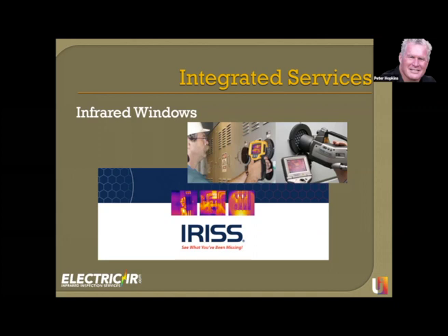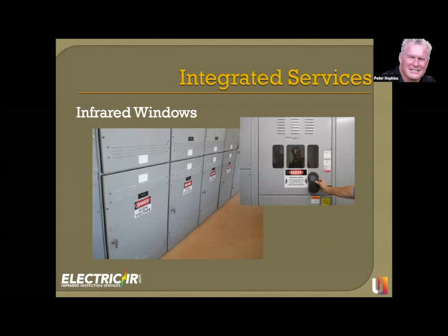That's nice, so there are opportunities, but these are things you'll run into and you need to know how to walk the walk, talk the talk. You might sometimes see on electrical switchgear where they put a window in - those are viewing ports, but infrared does not transmit through glass or plastic. You have to use specialized material, typically a crystal or polymer, depending on what kind of window it is.